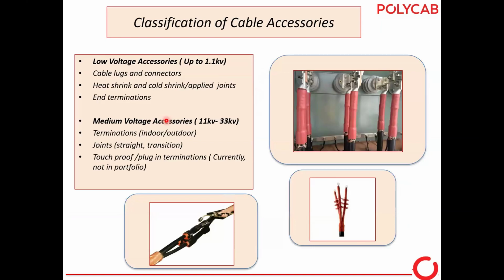So let's come back to the cable accessories part. Actually, heat shrink tube is also the cable accessories part only. So we classify this cable accessories on different classes: low voltage, medium voltage, high voltage, and extra high voltage. These are the different classifications.